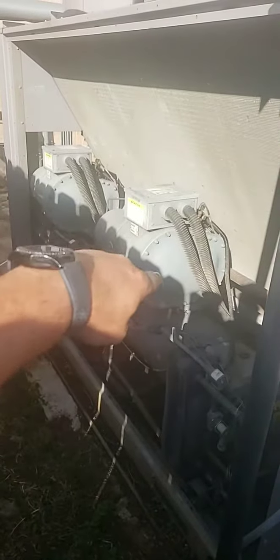So, like I was saying, this is a 134-ton chiller. You got 2 circuits. You have A here, B back there. These are screw compressors. So, basic chiller operation: this is an air-cooled system. We're chilling water through a lower barrel down here. This is our evaporator. This is our water inlet pipe right here. Our water outlet is down there on the end, coming out the top of the evaporator.